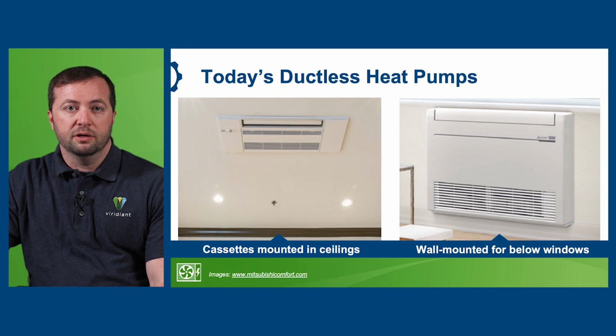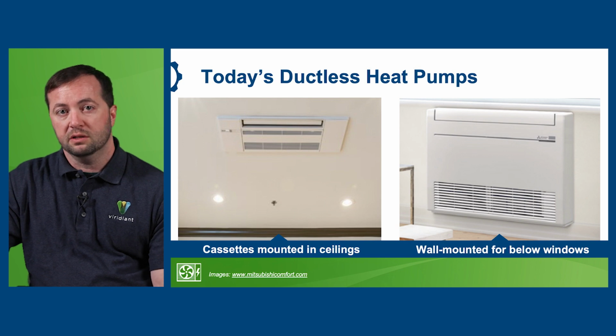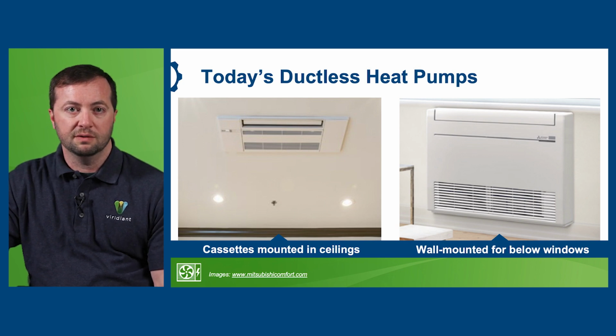It's usually also possible to mix a ducted air handler with ductless heads, so a ducted air handler could serve the main part of the house, with a ductless head serving a little used space or space that's somewhat disconnected from the main living space, like a bonus room over a garage.